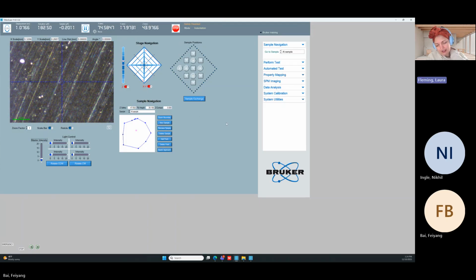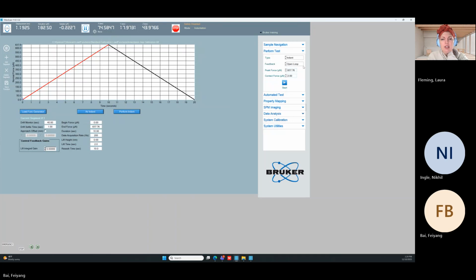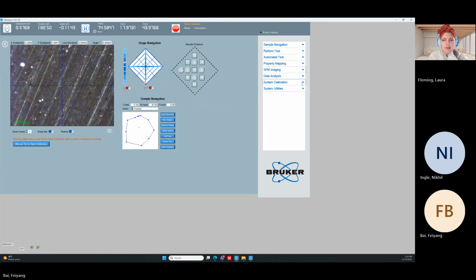Okay, so scratch testing. We did our indentation axis calibration, and everything else is well set up. Our samples are well defined. We don't need a tip area function. Everything is good to go there. So let's talk about scratch testing. If you go ahead and go to the system calibration screen. Yep. Let's go to system general.